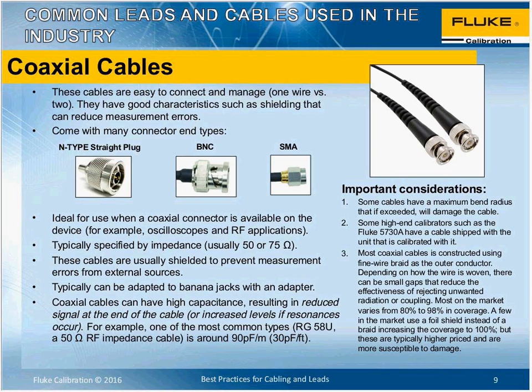It's ideal for oscilloscope calibration and RF calibrations and applications, which we'll talk about. Typically, these coaxial cables have about 50 to 75 ohms. When you look at the specifications for these, you will want to note what the resistance of the cable is, because that could play into your measurement.